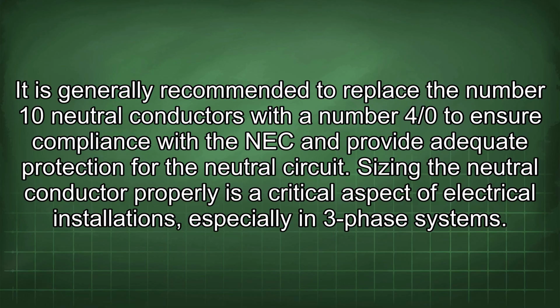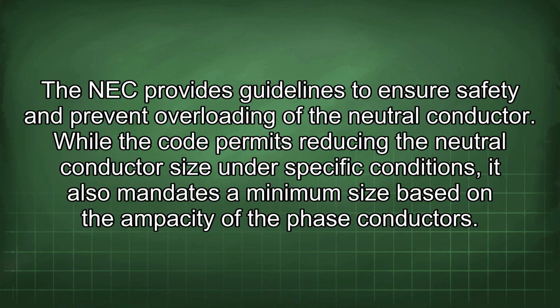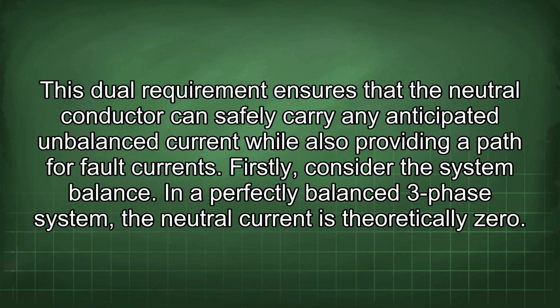Sizing the neutral conductor properly is a critical aspect of electrical installations, especially in 3-phase systems. The NEC provides guidelines to ensure safety and prevent overloading of the neutral conductor. While the code permits reducing the neutral conductor size under specific conditions, it also mandates a minimum size based on the ampacity of the phase conductors. This dual requirement ensures that the neutral conductor can safely carry any anticipated imbalanced current while also providing a path for fault currents. Firstly, consider the system balance.